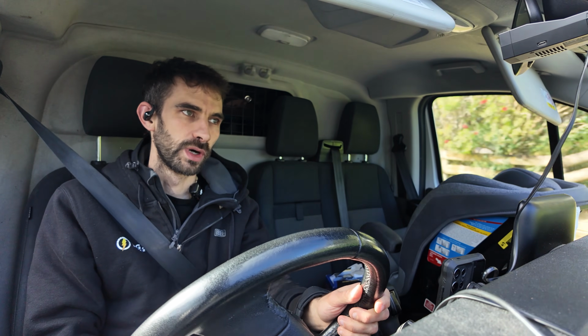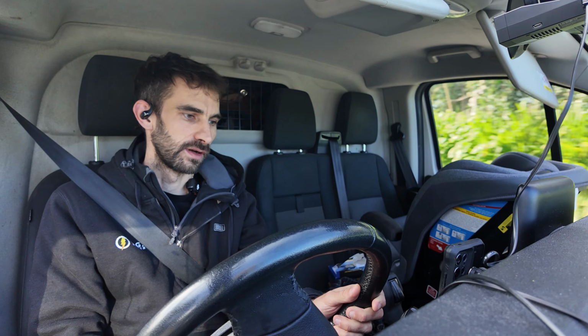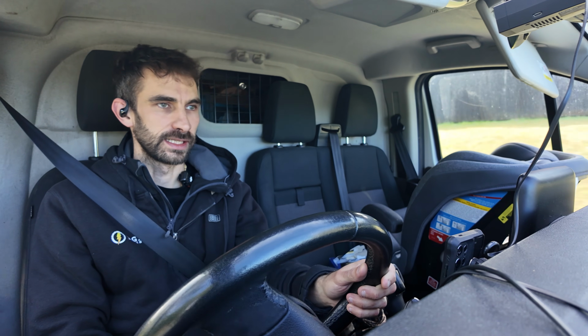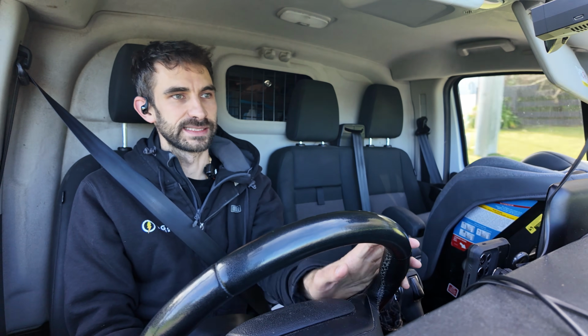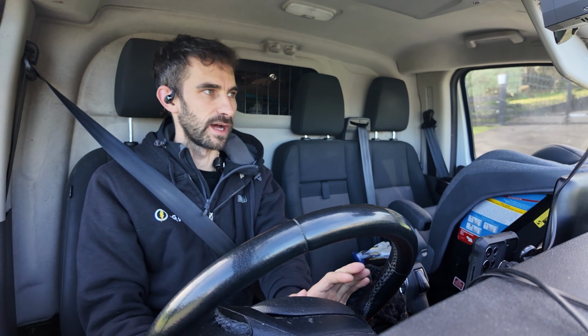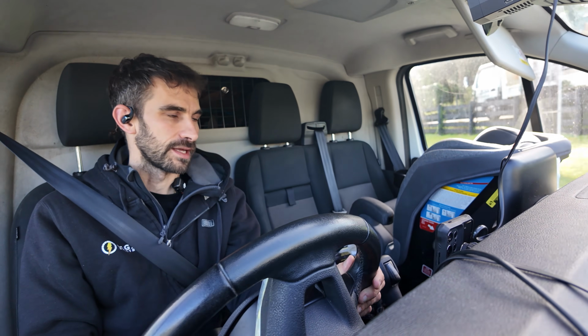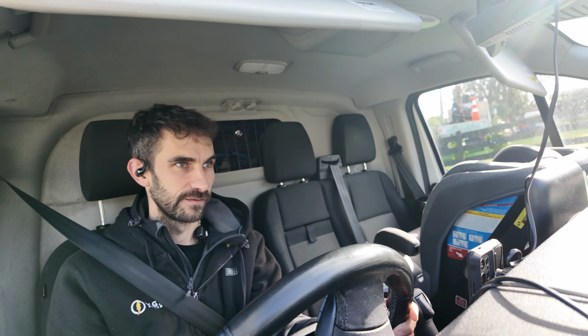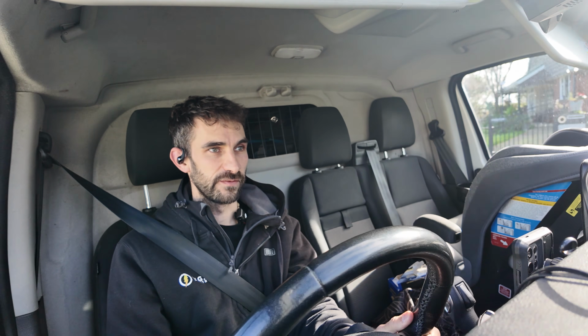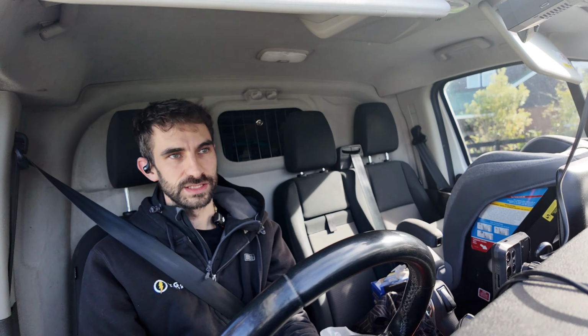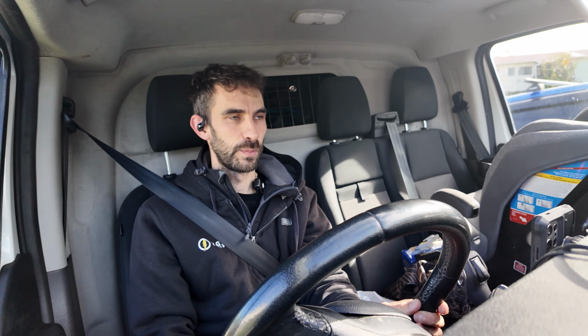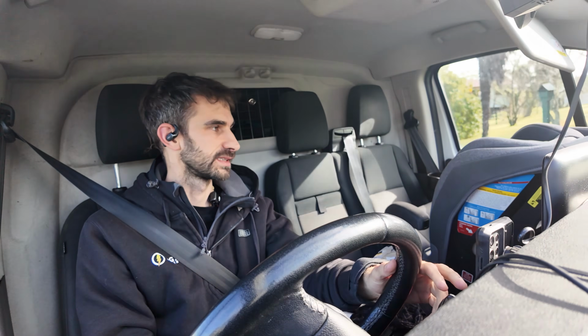But you can't do that for a whole installation, because one reason is you could have your installation fully isolated and you could have one metal appliance somehow have a fault where the frame becomes live. And then you could have a different metal appliance have a different fault where the frame becomes live, but from a different conductor. And now those 2 appliances create a fault path. So if a person touches both of them, they could suffer a serious electric shock.